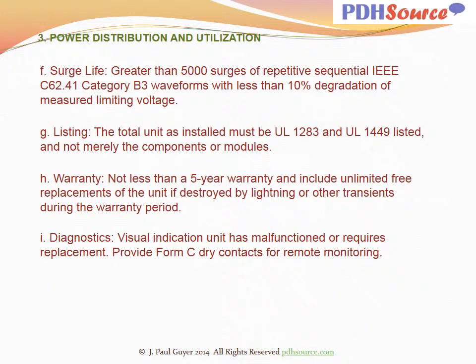Surge life greater than 5,000 surges of repetitive sequential IEEE C62.41 category B3 waveforms with less than 10% degradation of measured limiting voltage. The total unit as installed must be UL1283 and UL1449 listed, and not merely the components or modules. Not less than a 5-year warranty, including unlimited free replacements of the unit if destroyed by lightning or other transients during the warranty period. And visual indication if the unit has malfunctioned or requires replacement, provide Form C dry contacts for remote monitoring.